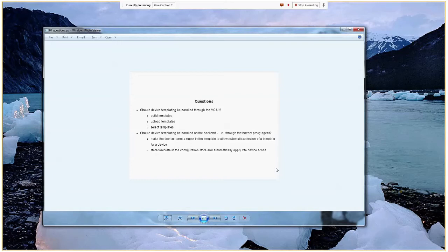And so although I've been using the UI for configuration, that's really tedious when you have 50 or 30 or 100 of the same thing. I realized that I can upload one registry file and then just configure the device. So I'm using one registry file over and over again for the same type of device that has the exact same points in it.